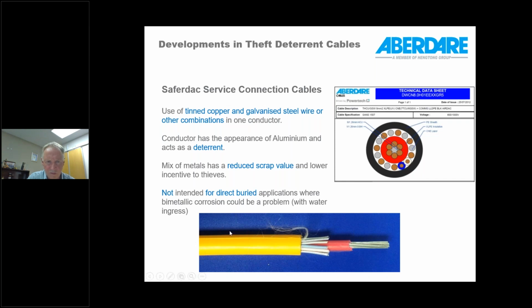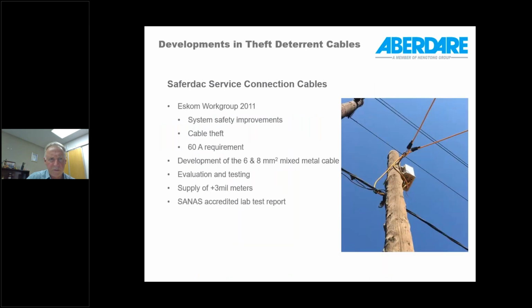Eskom doesn't use this yellow version, although one of the other metros or municipalities actually have used the yellow version, which is an indication of, let's say, this cable being different to the standard EDAC cable, and that's also helped those particular municipalities to combat theft. We would generally say that this cable is not intended for direct burial application, because bimetallic corrosion will potentially be a problem if water is allowed to enter the cable through a damaged sheath or at the end of the cable.